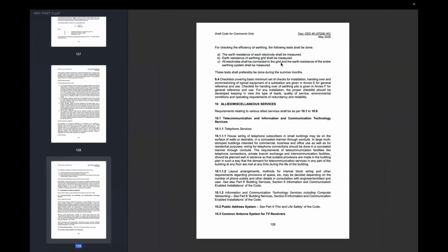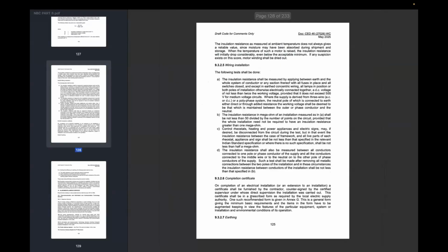You're supposed to verify the protective measure of automatic disconnection of supply by measuring earth fault loop impedance and checking continuity of protective conductors. This is what is given in IS 732.